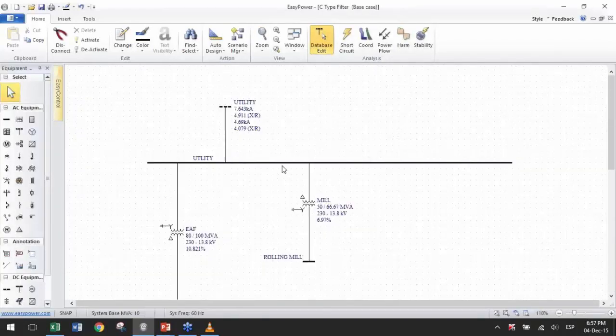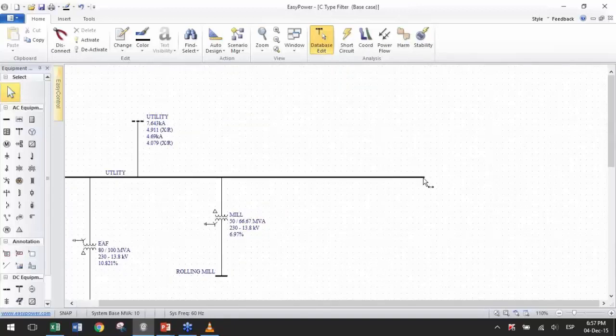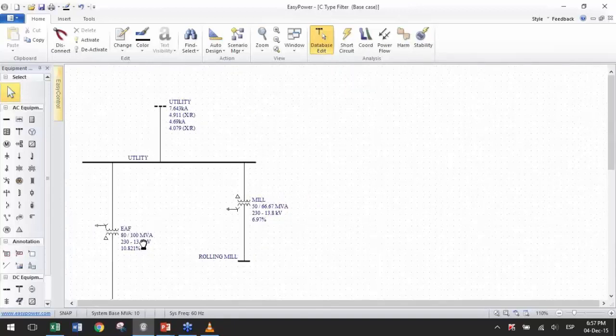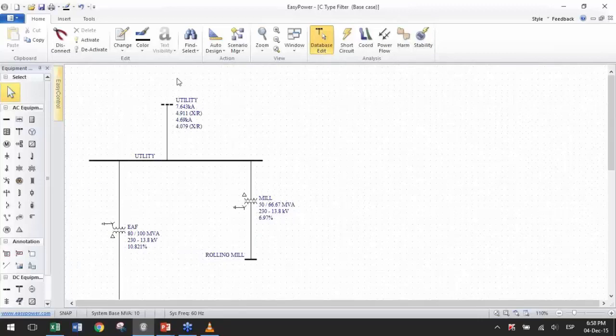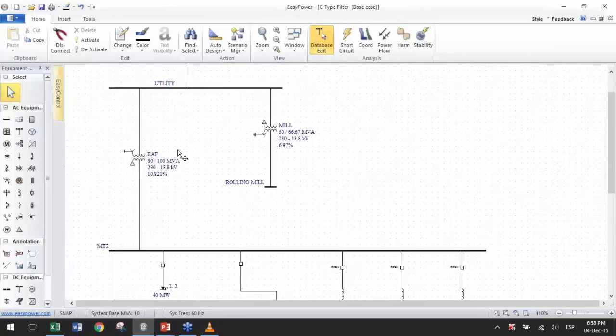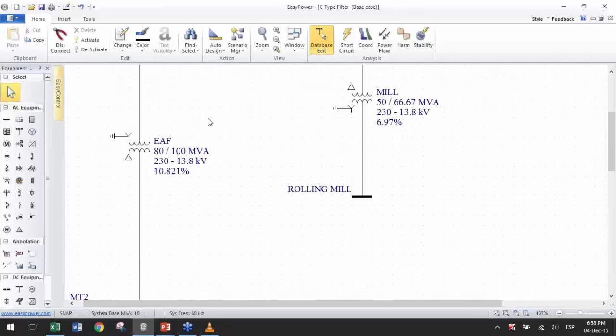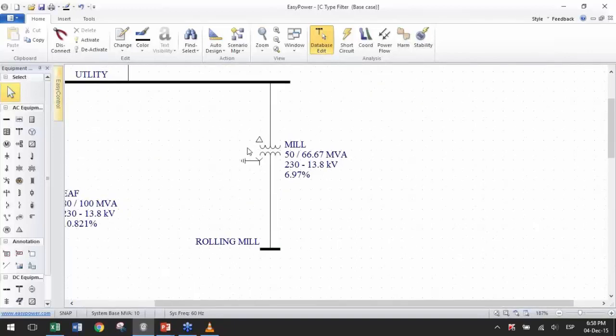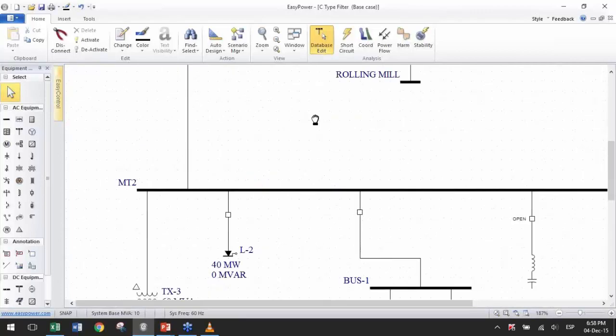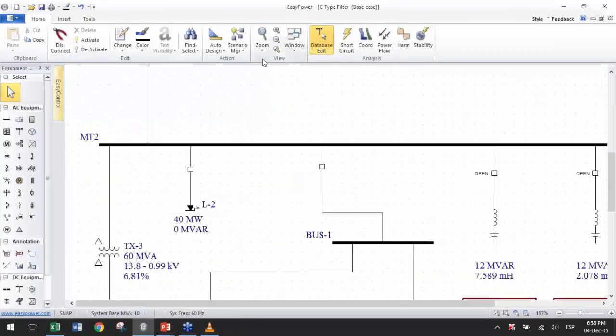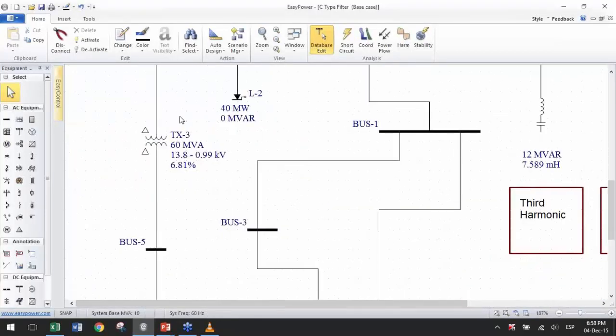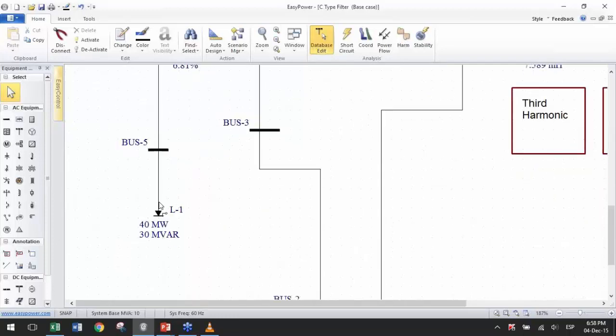Ignore all of this. This is the furnace facility that I was showing you earlier. It's a 230 kilovolts utility. We have a large transformer for the arc furnace and the ladle furnace, and a smaller transformer for the rolling mill, which I really don't care about. And now we have the furnace transformer and the electric arc furnace. Don't mind this for now. As a matter of fact, I'm going to turn them off.